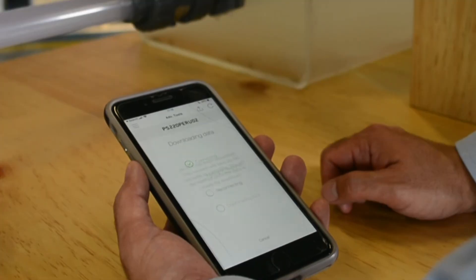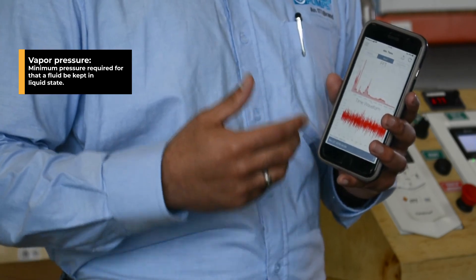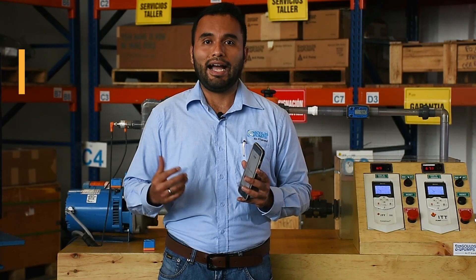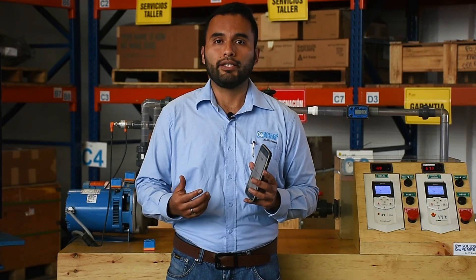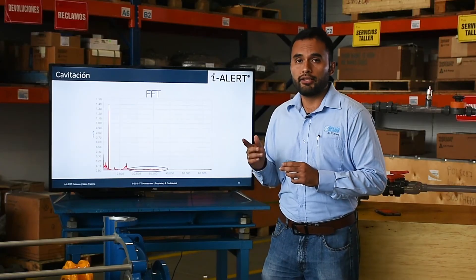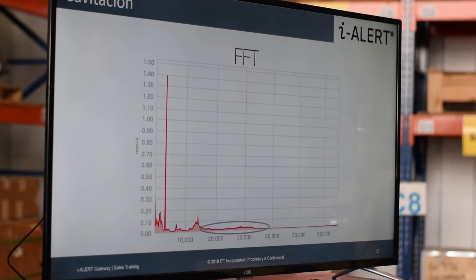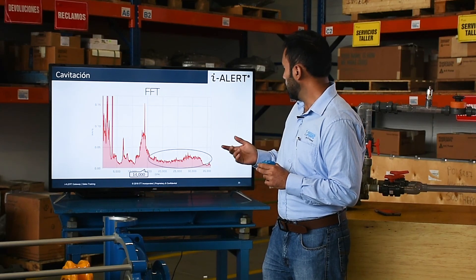Let's now look at the spectrum when cavitation takes place in the suction line. Cavitation happens when the pump pressure in the pipe or inside the pump falls below the vapor pressure of the liquid. So it begins to vaporize, forming bubbles that then implode upon reaching a high-pressure area inside the pump, which generates impacts on the impeller and the casing in a chaotic manner. One would expect to find amplitude at different frequencies, typically higher than the vane pass frequency. Indeed, the FFT we take shows a profile similar to a mountain range between 15,000 and 33,000 CPM, in this case with amplitude of up to 0.04 mm per second.